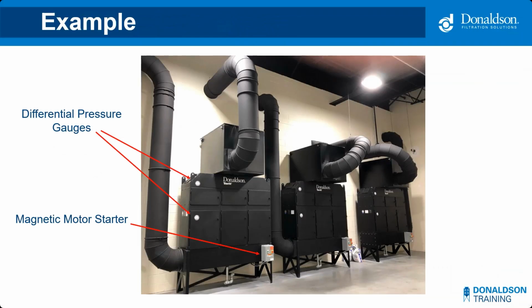This is a WSO mist collector, actually 3 of them, that are just in the process of being installed. You can see each collector has both a motor starter, the gray box that's mounted directly to the front of the collector, and 2 differential pressure gauges. You probably see 2 rows of doors on each collector. The bottom row allows access to the primary filter and the top row for the secondary filter. Each gauge will tell you the differential pressure across that filter so you can tell the status of them individually.